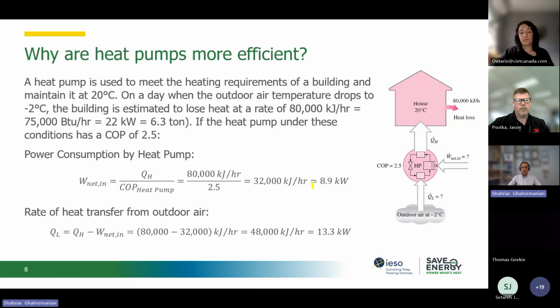For the same case, in reality, if the building requires these 22 kilowatts, which is equal to 6.3 tons of heating, we can put in baseboard resistance heaters, which are 100% efficient. That means we have to supply 22 kilowatts of heating. If we install a natural gas boiler or furnace, let's assume with an efficiency of 85%, then we need to provide 94,000 kilojoules per hour, which is almost 26 kilowatts. So it's going to be 26 kilowatts that is needed if we want a natural gas burning system with 85% efficiency. But let's compare that with a heat pump.